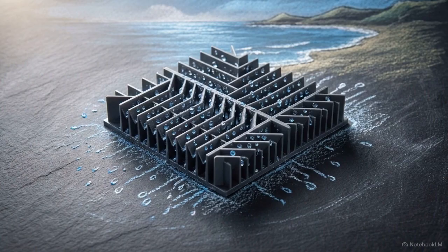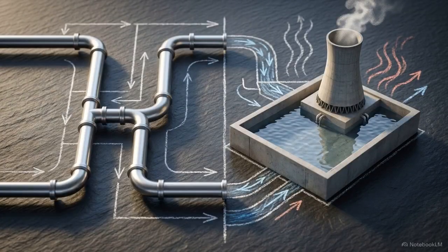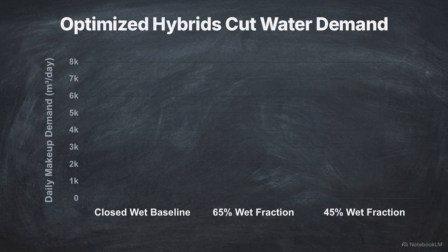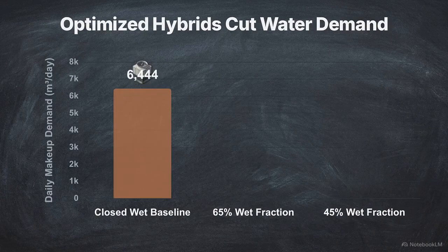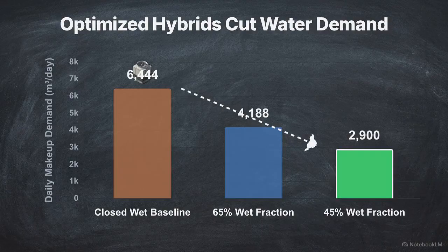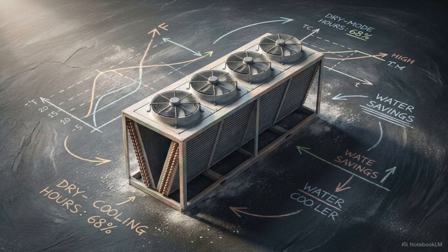This is a 0.03% difference from the open tower, caused strictly by better drift eliminators, rather than a reduction in evaporation. While closed wet towers protect the facility loop from contamination, they do not materially reduce water consumption at an equal heat load. True water savings require a hybrid closed adiabatic system. These units use dry coils to reject heat without water when weather permits. As this chart shows, if the climate allows an optimized 45% wet fraction, the daily makeup demand drops to 2,900 cubic meters. Sustainable coastal cooling is achieved by utilizing dry mode hours to reduce the total wet operating fraction.